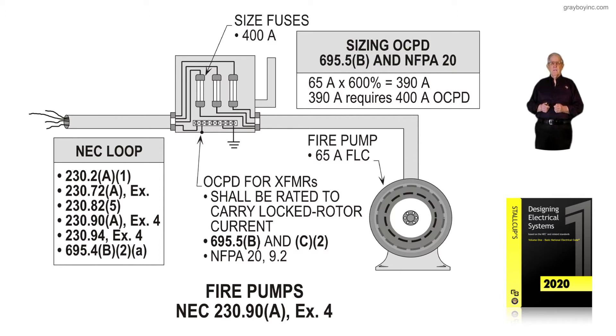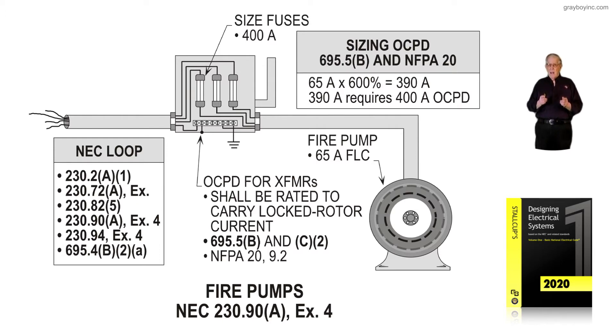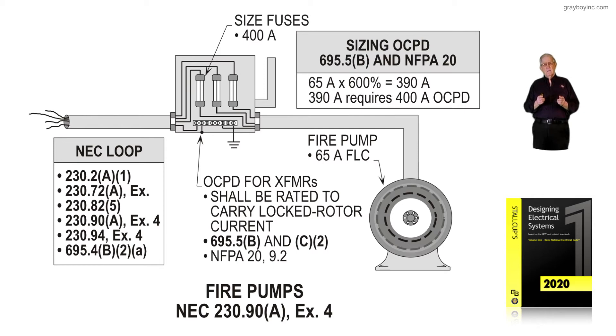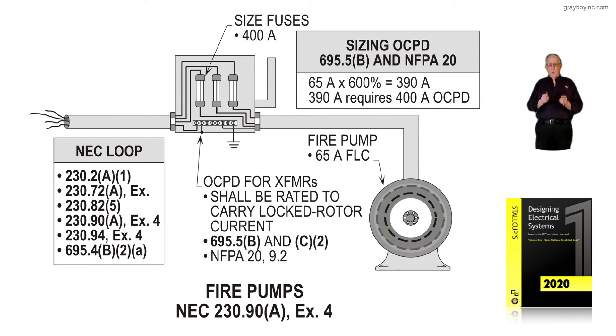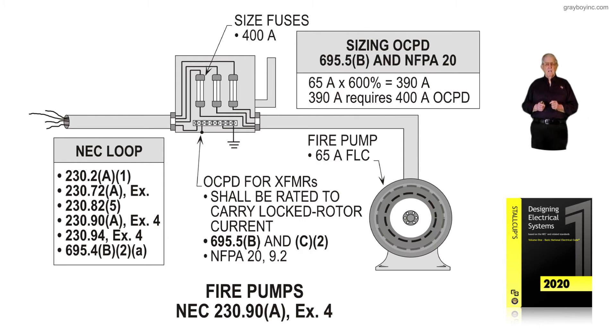NFPA 20 9.2 lists these rules, but also lists what is considered reliable power to a fire pump. As discussed previously in Volume 1 of Stallcup's Electrical Design book, reliable power is when the utility power has not gone down in a collective four hours, as found in NFPA 20, which gives us these rules.